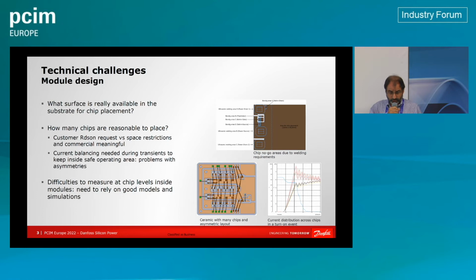Another important thing is making sure you have current balancing between the different chips, especially during transients, during turn on and turn off. Here I'm showing an example of a module with about 14 chips or more. On the right is a simulation showing that because chips have different local commutation loops and gate loop inductances, during turn on some chips see higher currents than others, meaning some chips are more stressed than others. The art of module production is to try to avoid this happening—I'm showing this as an example of what you try not to get.